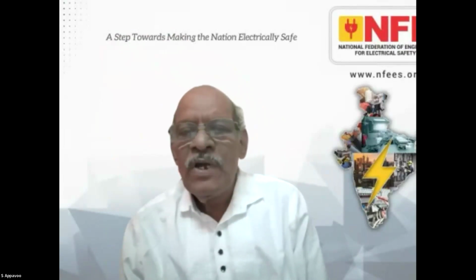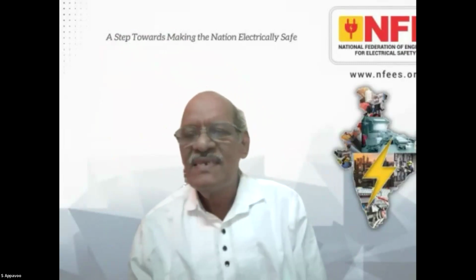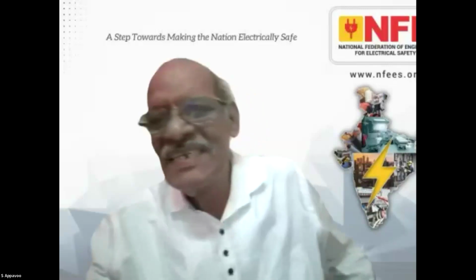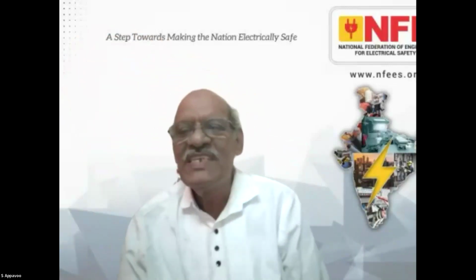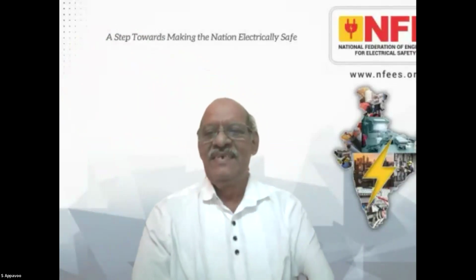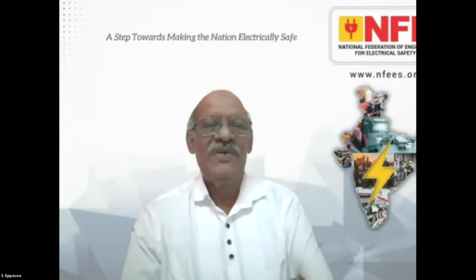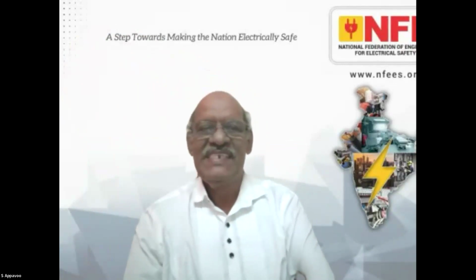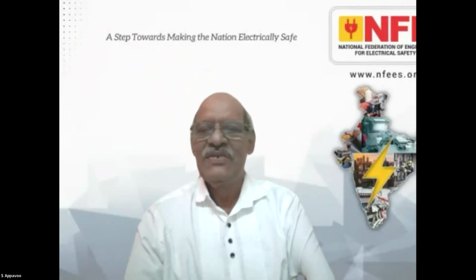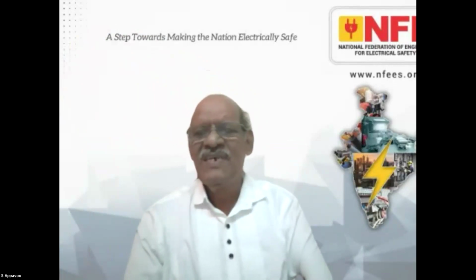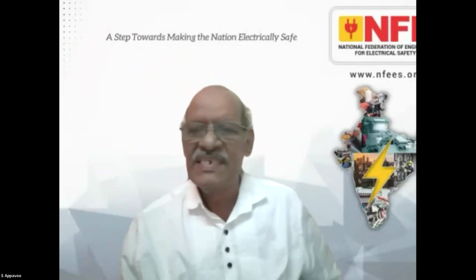Another question is from Chetan Pawar. During testing, we need to remove the connection. This is actually very vague, but I will consider that you are asking about a continuity test. Then you are supposed to disconnect the test link. Or if you are doing an earth resistance test, you are supposed to disconnect the test link. If that is what you are asking, that is the answer. If it is an earth electrode, then contactless measurement is possible and removal is not required. You can have window type or tong tester type devices, CTs. You can clip on and measure the earth electrode. It is applicable for EHV substations for a periodical check, not for LV installations or lighting.